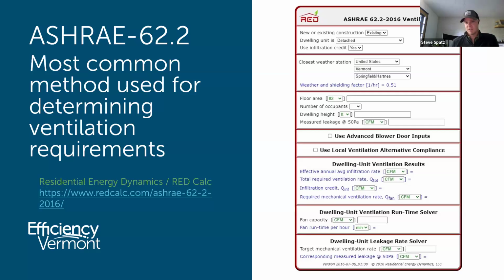So in using this tool, you're defining the type of construction it is, specifically what climate it's built in, because that has an impact on the ventilation needs. Size of the building, number of occupants, exposure. If you are doing blower door testing and you're using blower door numbers and/or estimated numbers, you can account for that in the inputs here too. That would be considered the infiltration credit. So we'll talk about that here in a moment. But it's a very handy tool to use that's readily accessible, that gets you to the outcome of what you actually need specifically for the building that you're building for ventilation air.